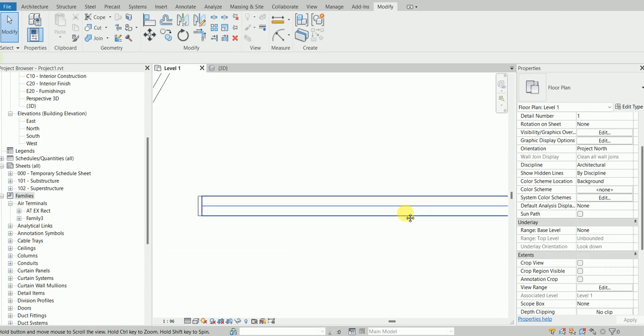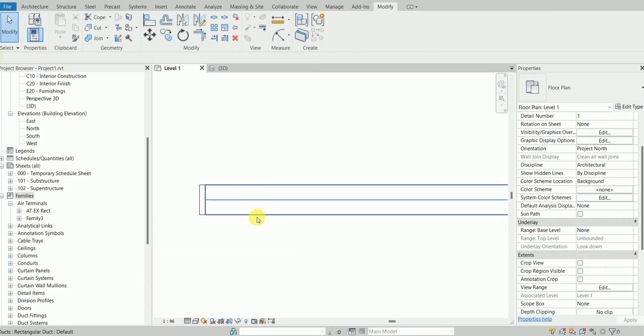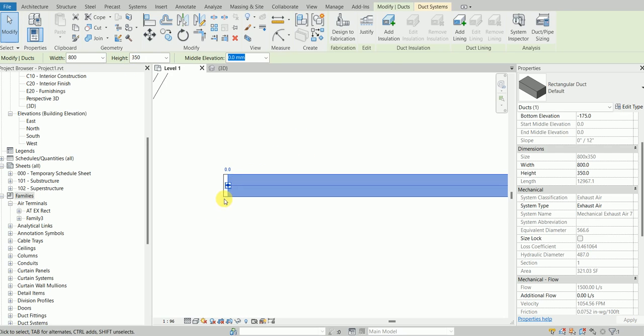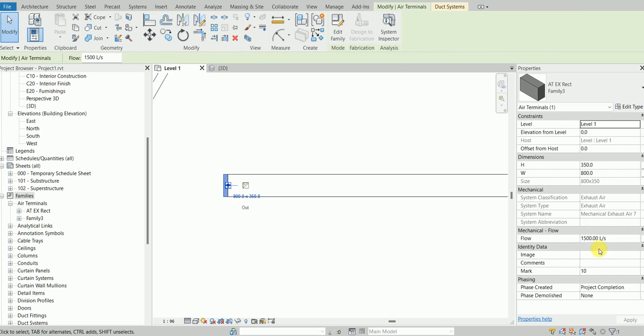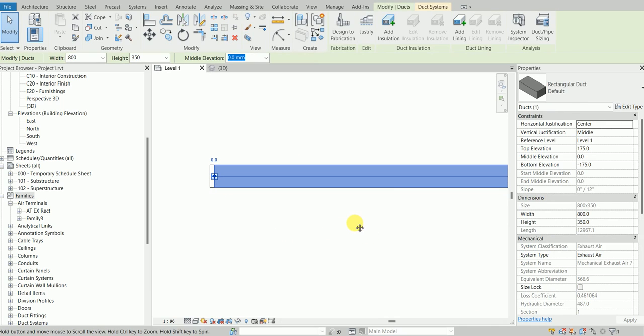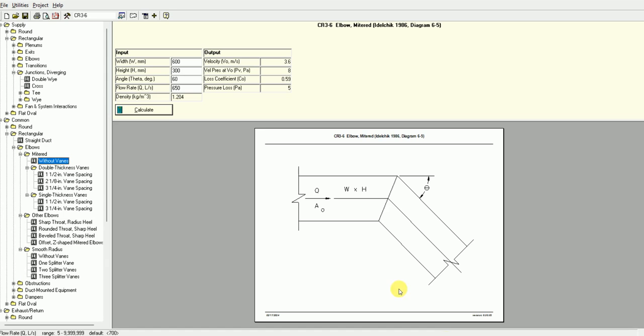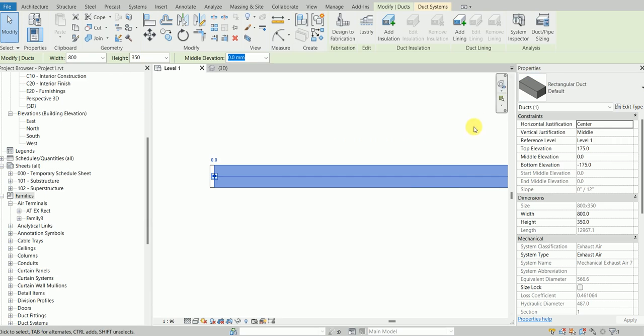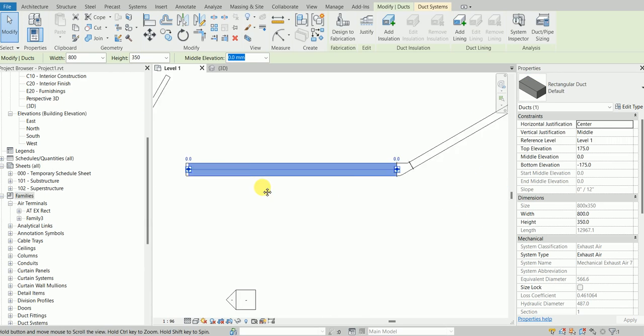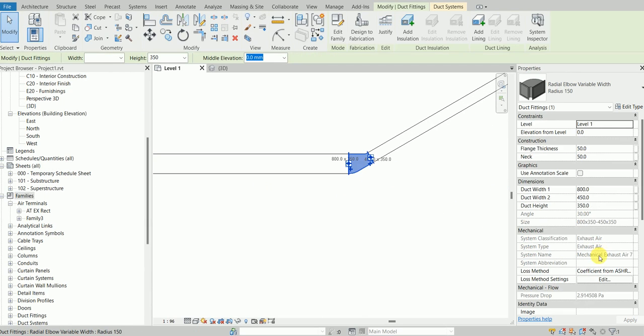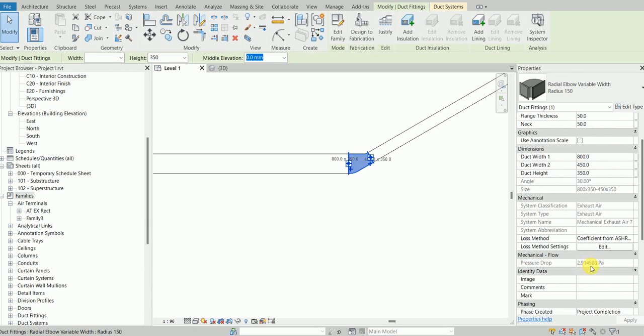I have 800 by 350 at 1500. So 800 by 350, 30 degrees with 1500. This is 3 pascals and we have this pressure drop of 2.9, which is very close to 3 pascals.